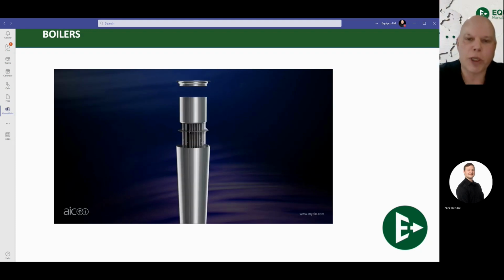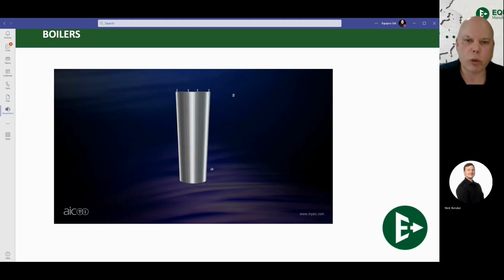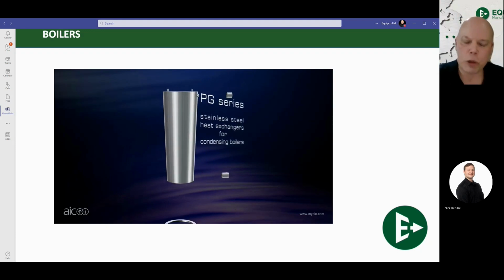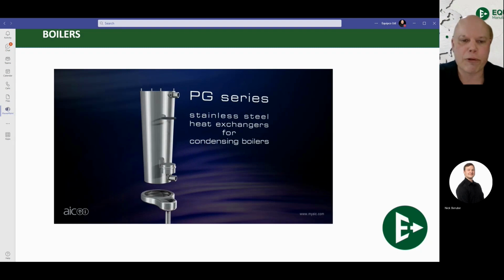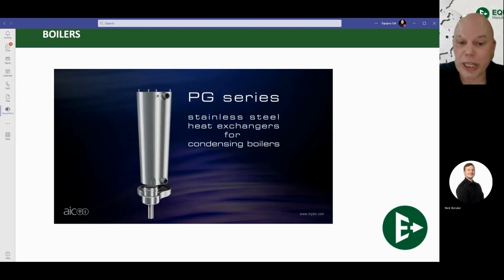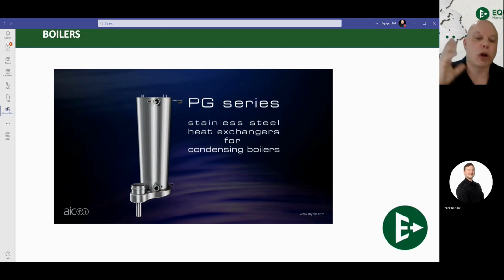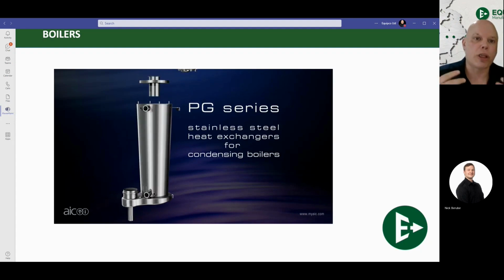And here's our shell coming across. The shell is what holds the water. The tubes that went down, those are our fire tubes. That's where our flue gases come from. Our base pan is stainless steel, which can handle that condensate. So it's all designed as a good package to operate during combustion.